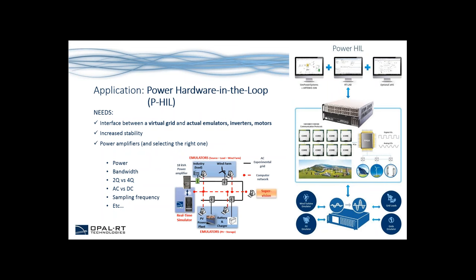The third application is power hardware-in-the-loop, involving an interface between a virtual grid and actual emulators, inverters, and motors. This requires increased stability due to power amplifiers in the loop. Selecting the right power amplifier is a key challenge, considering power, bandwidth, two-quadrant versus four-quadrant, AC versus DC, and sampling frequency. Opal RT works with various third-party amplifier manufacturers to help select the right one. The real-time simulator interfaces with a power amplifier, which connects to wind turbine emulators, PV emulators, grid loads, motors, and inverters.